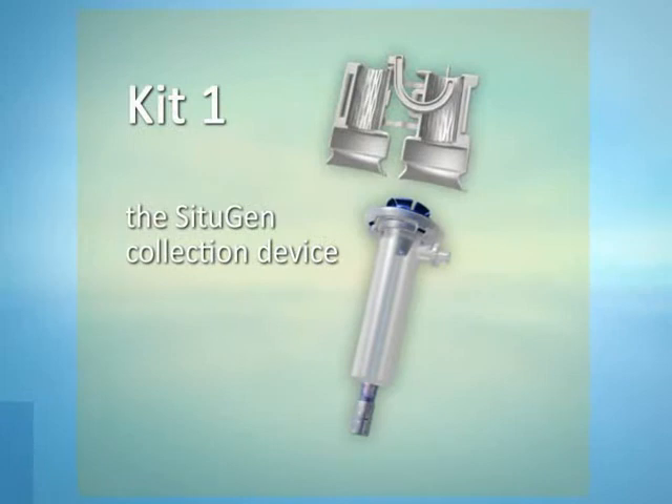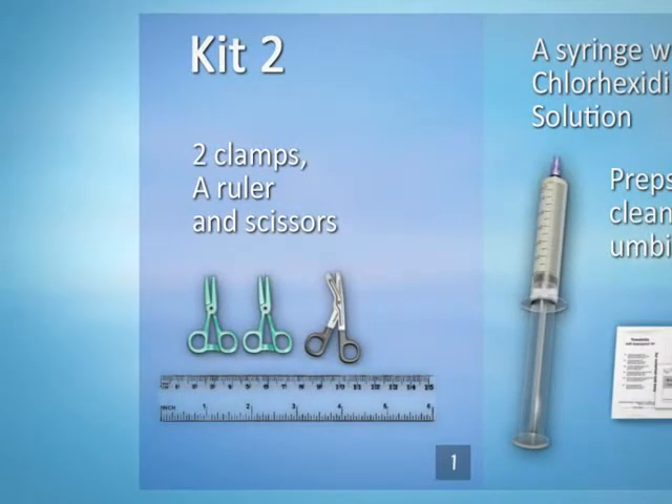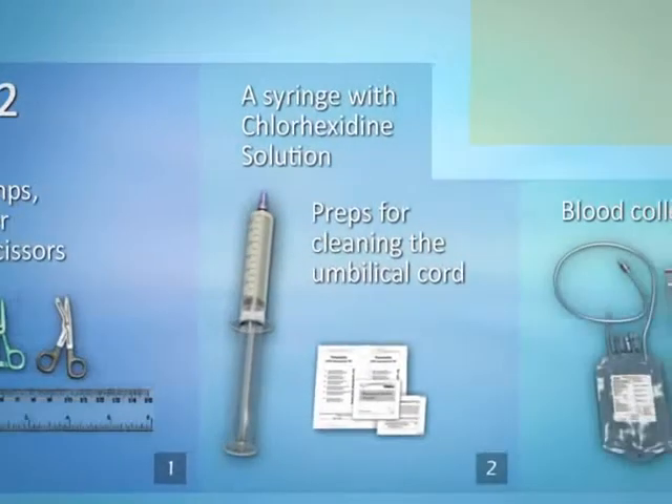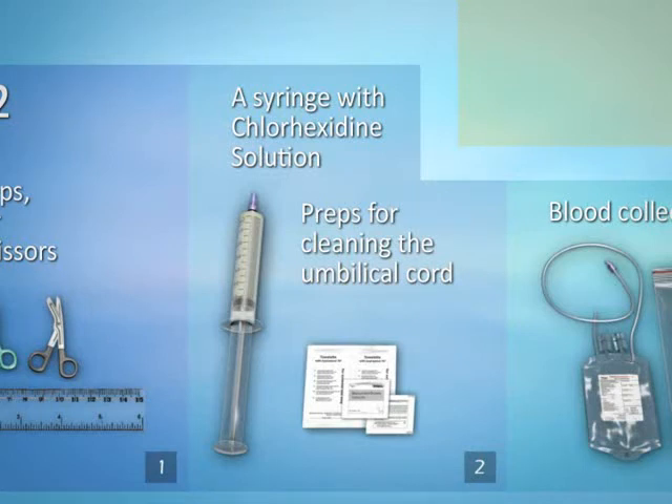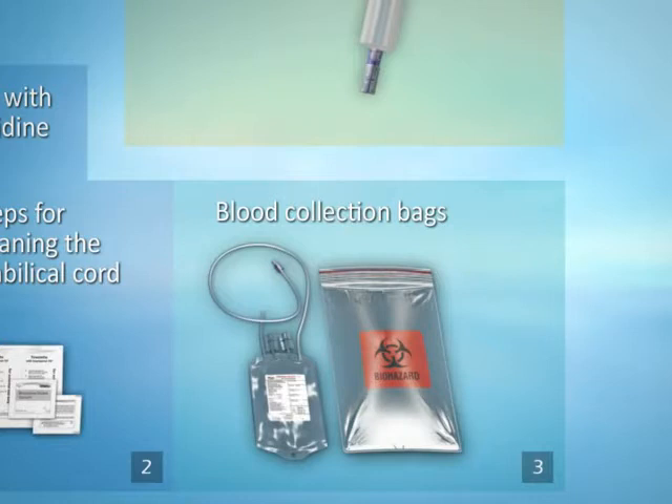The SituGen device in the first left side blister is supplied in two separate parts: an upper part and a lower part, also referred to as the clear chamber. In the second right side divided blister, the first compartment holds all the items that assist in the preparation stage in order of usage: two clamps, a ruler, and scissors. The second compartment contains all the items that assist in disinfecting the device and cord — a syringe with chlorhexidine solution, as well as small and large alcohol preps for cleaning the umbilical cord. Finally, the third compartment holds all the items for final collection and delivery to the lab: a blood collection bag with anticoagulant and a plastic sealing tape bag.